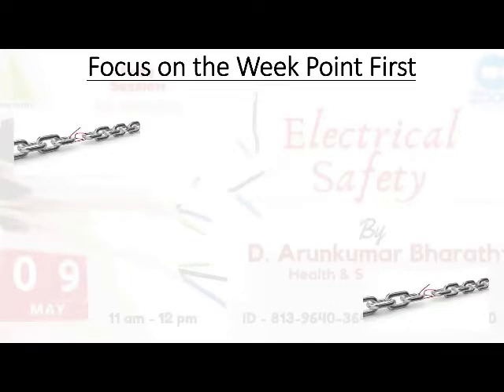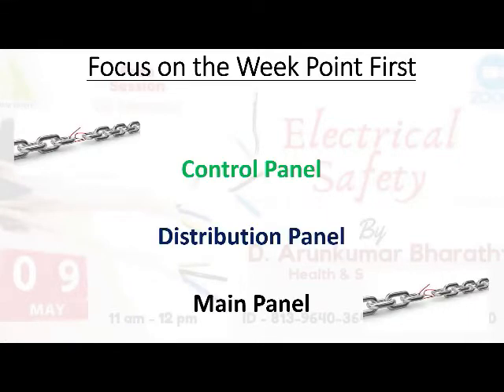Then focus on the weak point. What do I mean by weak point? All connections or junctions are normally weak points. If you take any mechanical valve, like a fluid or gas valve, the connections, couplings, and joints are always the weakest points. So after lockdown, once you want to start operation, always check the connection points like the control panel and junction box first. Ensure all connections are right and there are no insects or anything inside. Then go to the distribution panel, and finally the main panel. Always check wherever there is a connection or junction, as these are considered the weakest points.